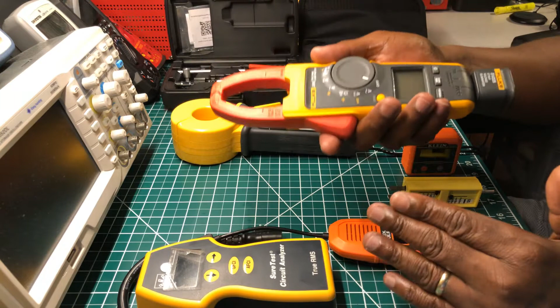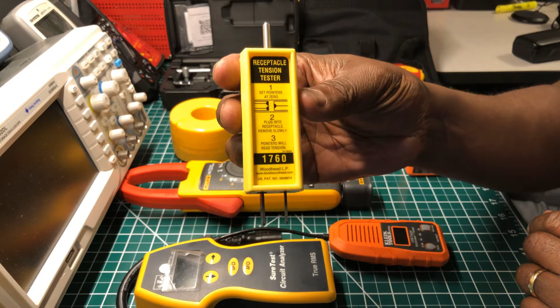Sometimes even new devices out of the package, like receptacles, can be bad. So I pull out this receptacle tension tester, which is also referenced in the code book. It's made by a company called Woodhead, part number 3808874. You want to make sure the receptacle's blades have enough tension, because if it's not gripping right it can cause a fire. You want to check that even the ground plug is right.